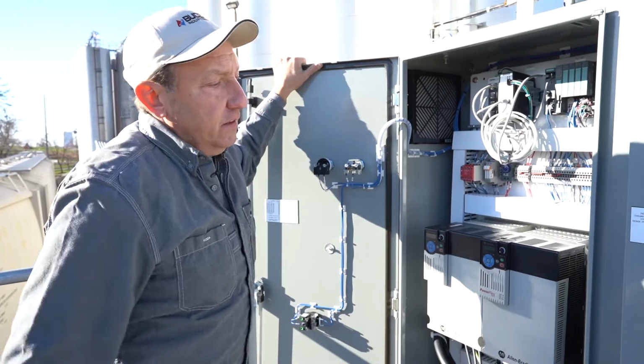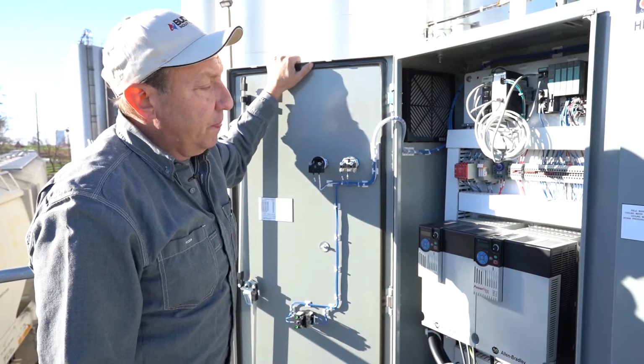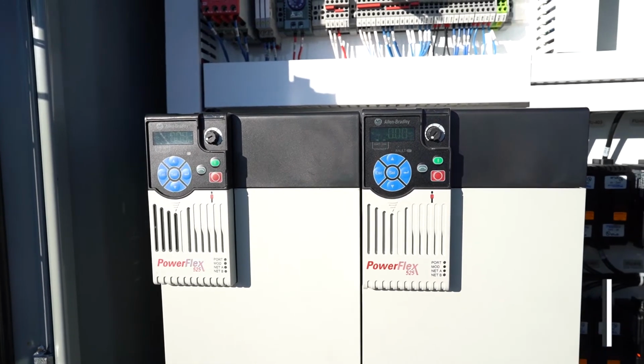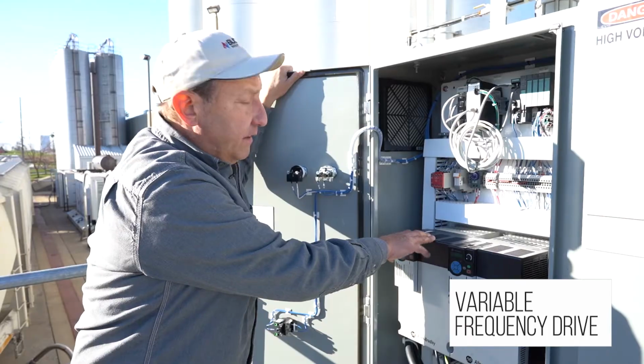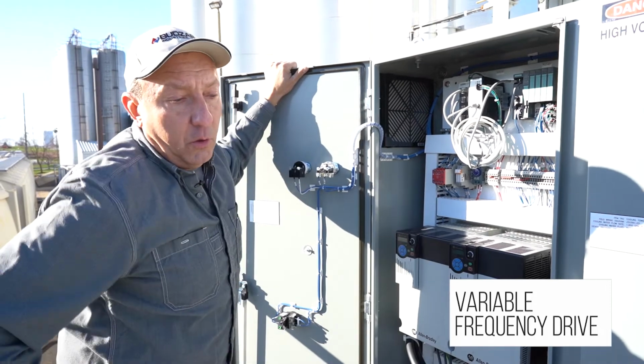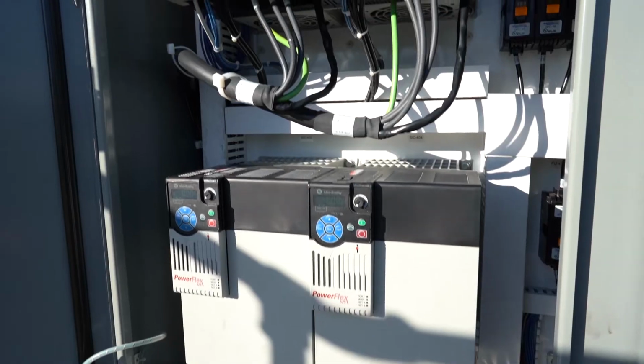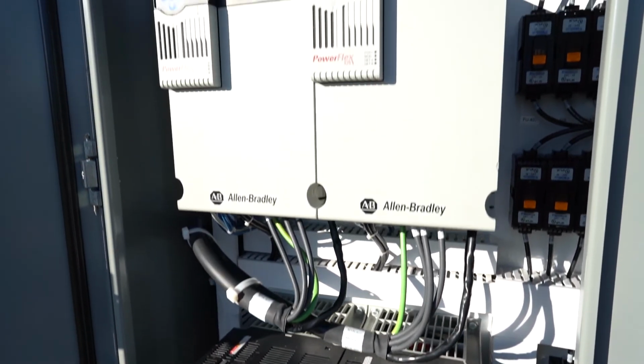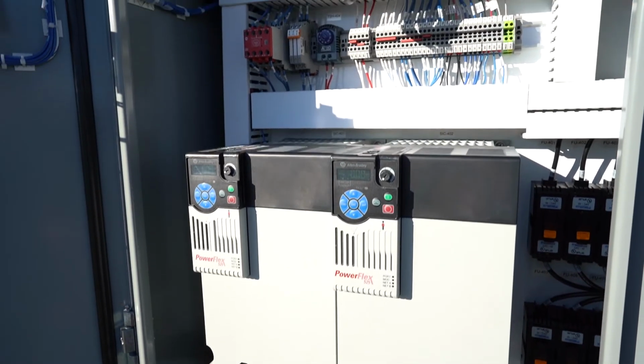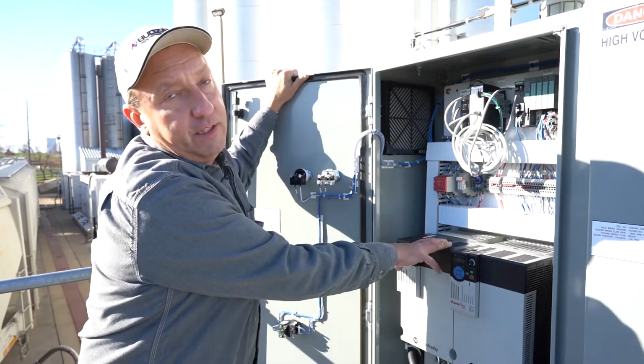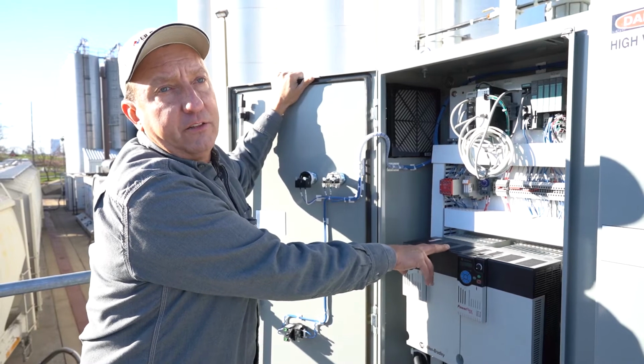Okay, inside the control panel here for the tower system, we control each pump with a variable frequency drive. And this is how we control the water going through each condenser. Rather than using tower fans to reduce and accelerate the capacity control, we're using the VFD to control the water being circulated through each condenser.